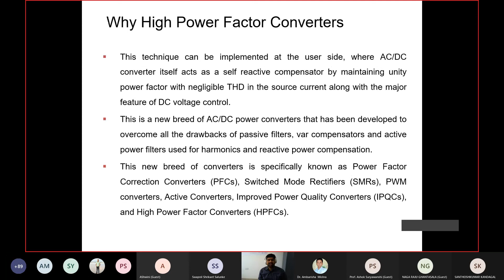So basically, while we discuss about this high power factor converter, basically it is nothing but an inverter, and the inverter's bidirectional power flow, from DC to AC side or AC to DC side, is utilized to direct the current properly so that the power factor at the source is unity. Typically, the high power factor converter looks like what you're seeing on screen. This specific inverter connects to the grid system on the AC side through a boost inductor.